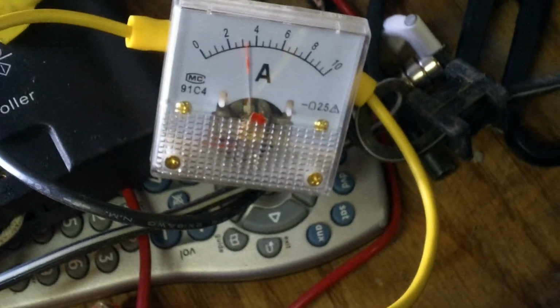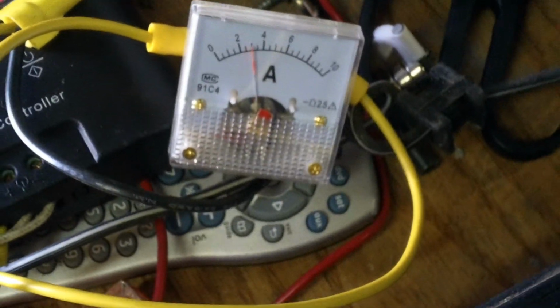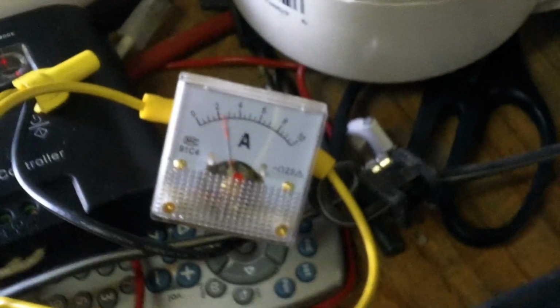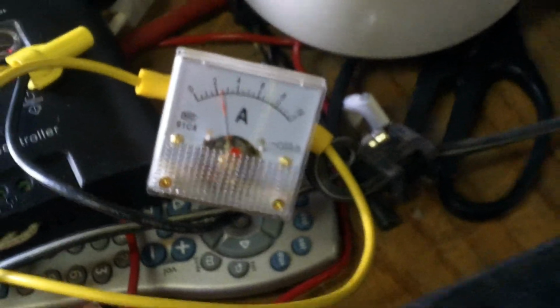And it'll usually run about a steady 4 amps, maybe a little bit more, depending on the size of my battery bank. If I had these both wired in series, this would probably draw a full 6 amps. But as you can tell, as the batteries are charging, your current goes down. So that's what this is going to be set up as. I ain't going to have meters and stuff on it, of course. It's just going to be a straight solar street light setup. And right now, that's just set up in 12 volts, and 24 volts does the exact same thing.